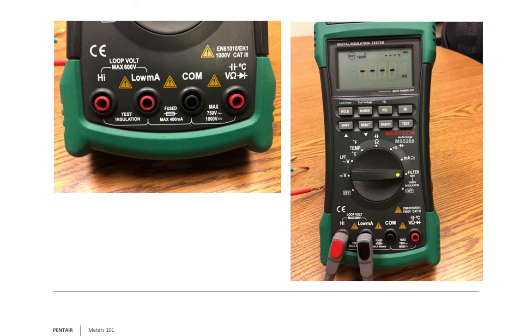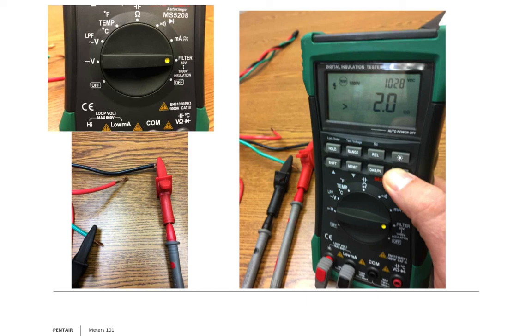Here I have it set up to read insulation test of 50 to 1,000 volts. I pulled the probes out in the picture to the left so you could better see where it says test insulation. They're both red, and that's where I would set it up to measure. Now, in the picture to the right, are you surprised that I'm reading 2 gigaohms on a very short piece of brand new, well-insulated wire? When I push the test, it's putting out 1,028 volts and measuring over 2 gigaohms. So that wire is perfectly fine, okay?